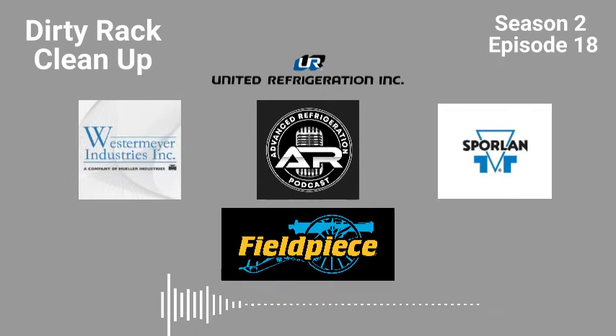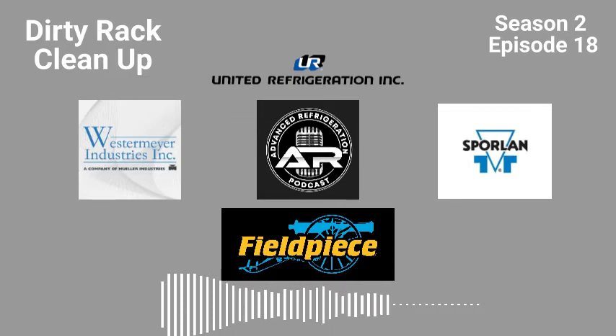I am a big proponent of getting the dryer out of the case. I do not want dryers in cases or walk-ins. Nothing pisses me off more than going to set superheats or doing commissioning or startup, and I look in there and there's a dryer and I don't know if it's plugged or not. Now I have to break out a torch, cut the dryer out and hard pipe it.